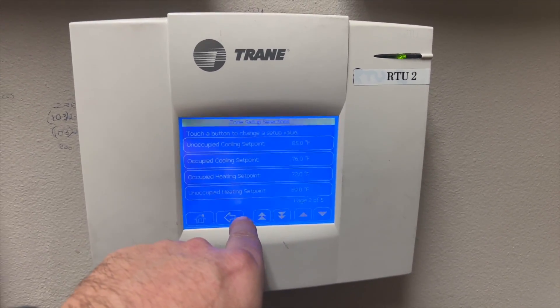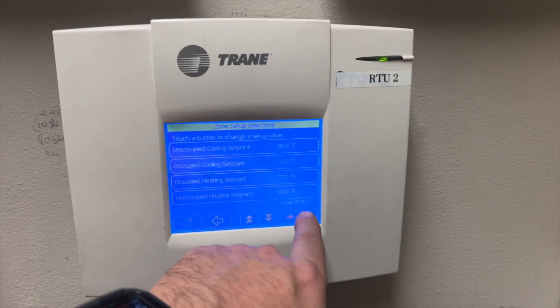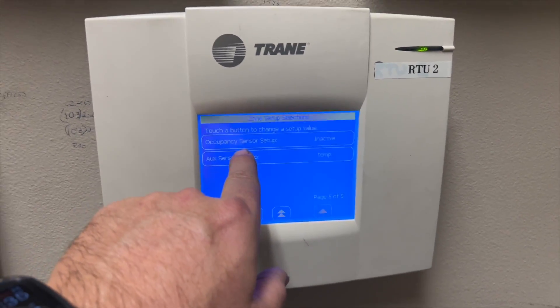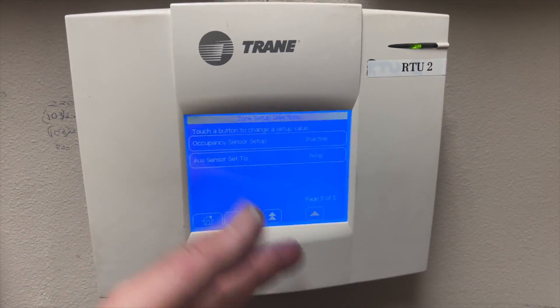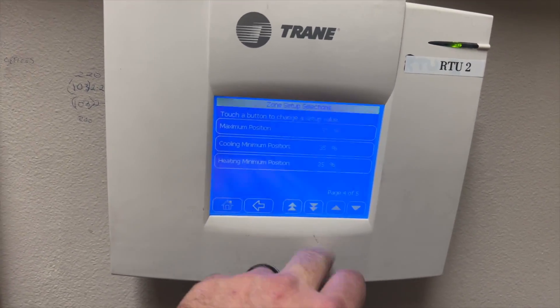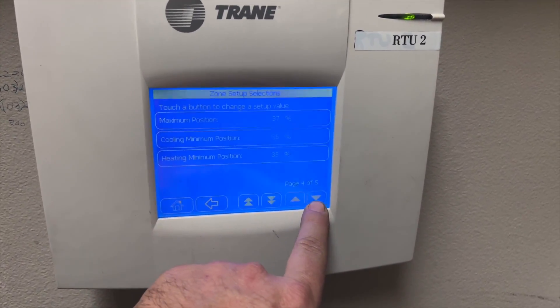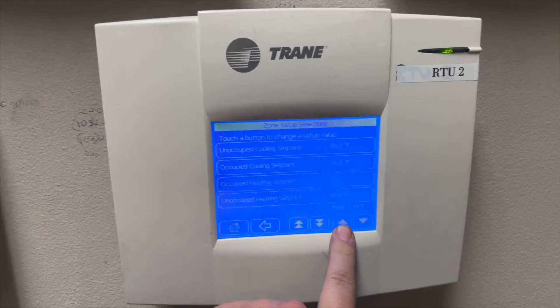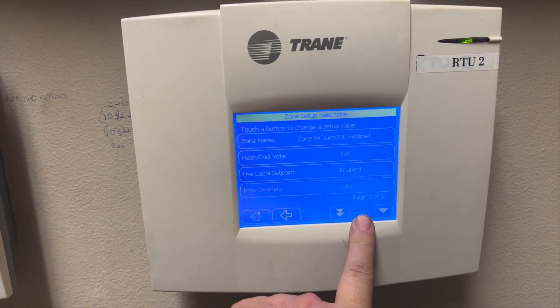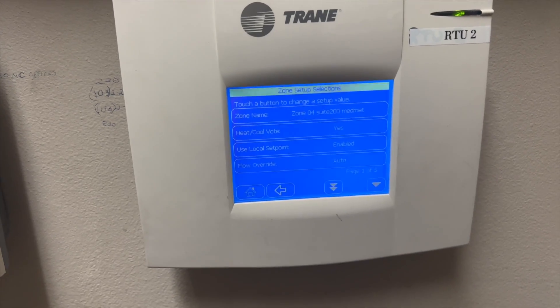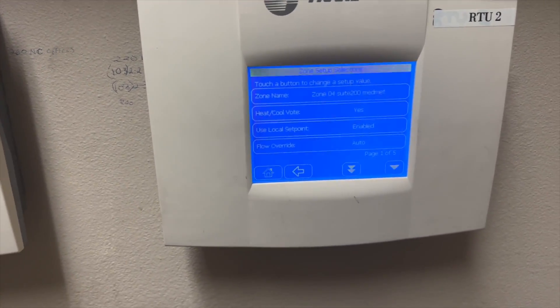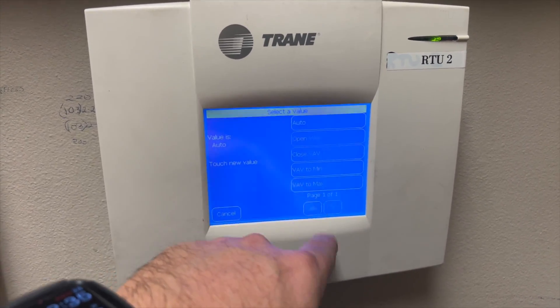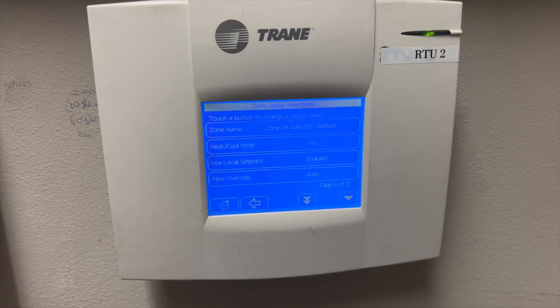You have your occupied setting for heating and cooling. There are five pages — hitting the double arrow takes you to the last page. You have Occupancy Setup, Sensor Setup — no sensor is installed so it shows inactive. This is where we do our airflow adjustments: minimum, maximum, and your low limits for heating and cooling. Under Flow Override you can open or close the dampers — open all the way, close all the way, set to minimum, or set to maximum.